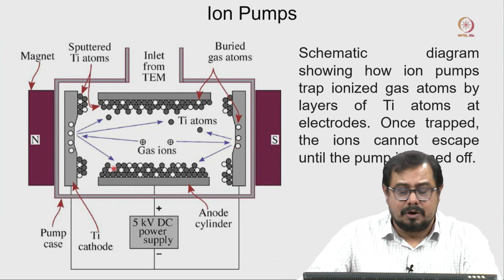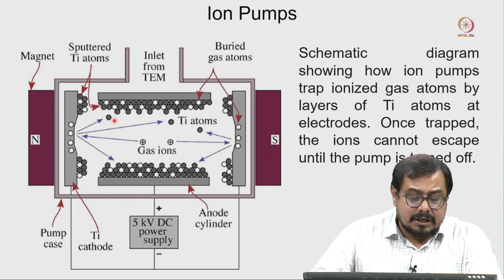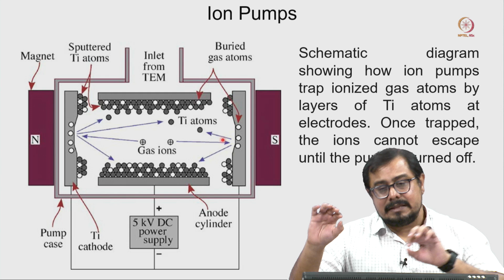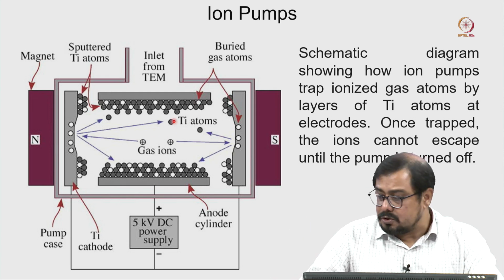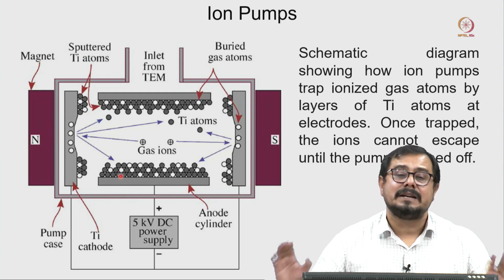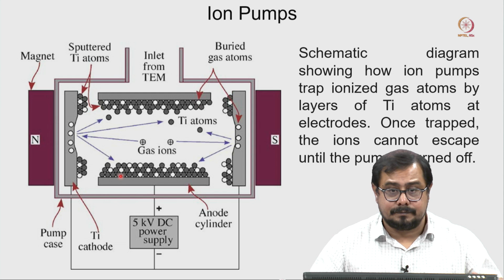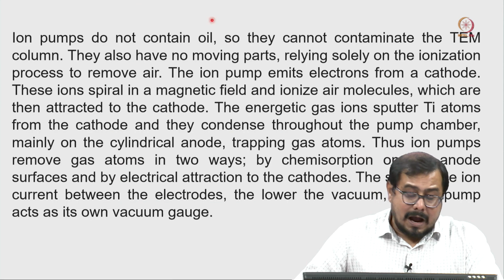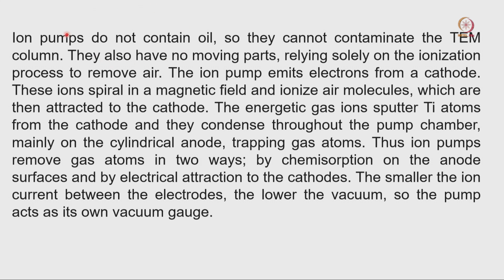One thing you also have to remember is that the ion pump is sometimes called the trapping pump, because the ionized gas interacts with the titanium ions and is fixed there. That is one of the reasons it is called the trapping pump. Ion pumps do not contain oil, so they cannot contaminate the TEM column. They also have no moving parts.